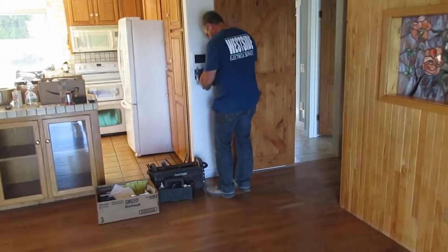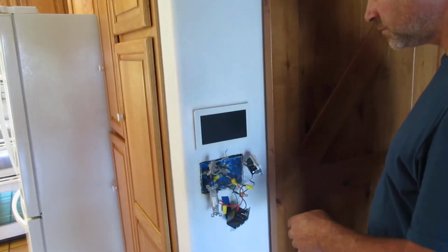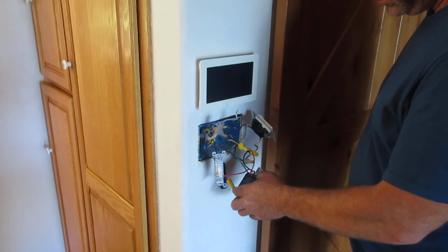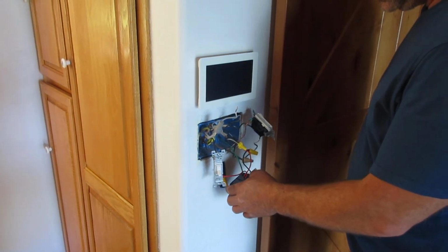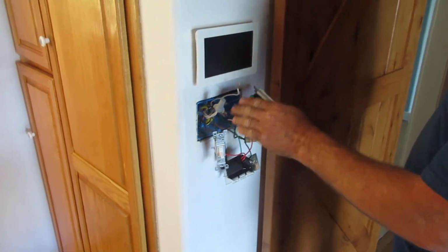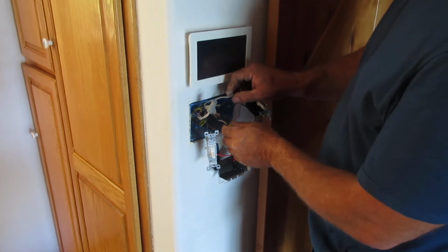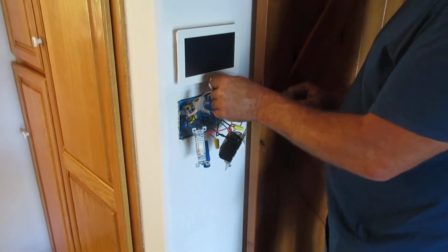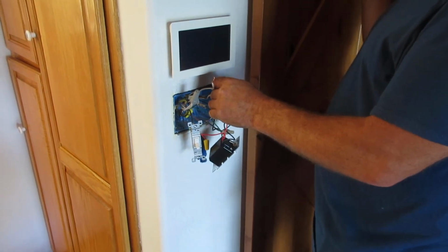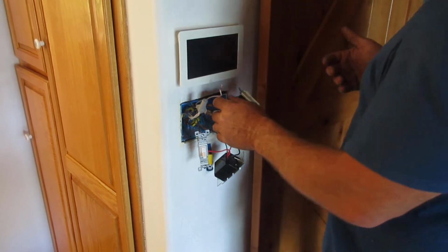And we're here with Marty of Westside Electric, local specialist electrician, and he's going to tell us what we found as far as electrical code violations. Go ahead, Marty. Okay, in this box we found that they had used a code violation for wiring the three-way switch. They had done it with just a 2-wire in between the two switches, so they did not bring the neutral with the circuit, so therefore we had the imbalance.